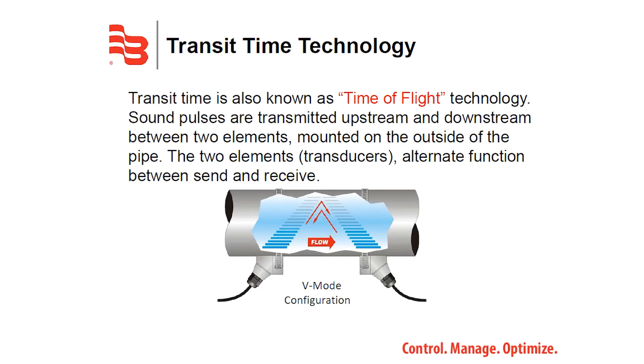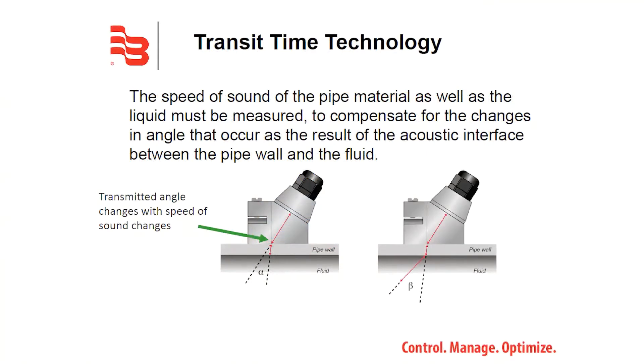The speed of sound of the pipe material as well as the liquid must be measured to compensate for the changes in angle that occur as a result of the acoustic interface between the pipe wall and the fluid.